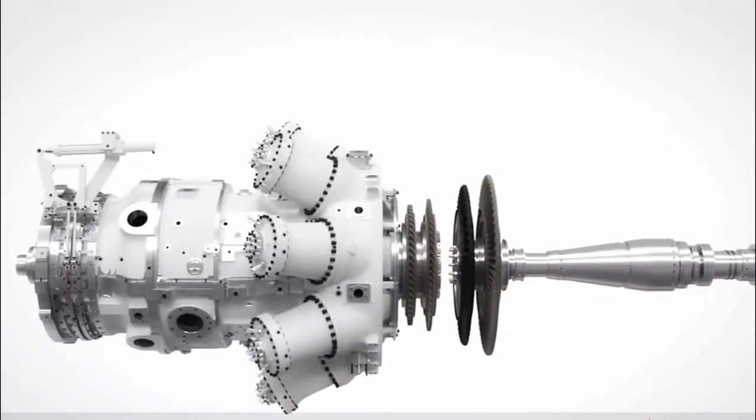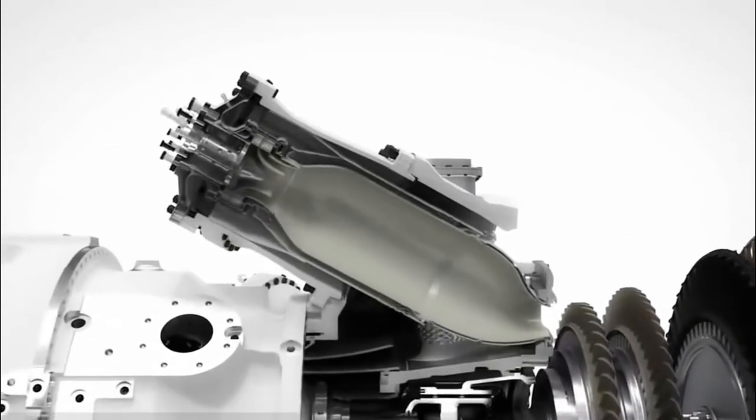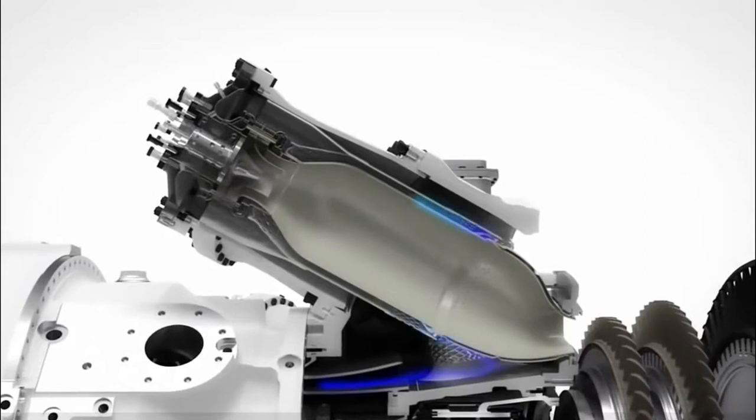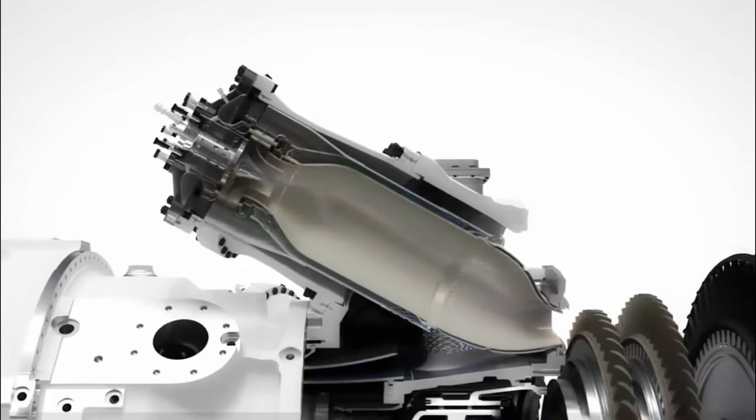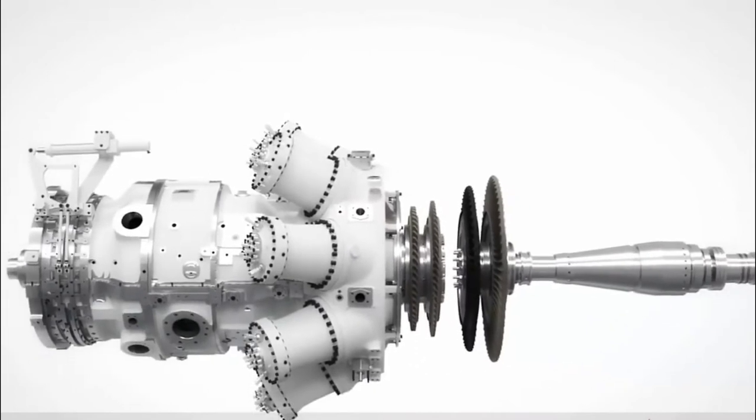The new combustor, featuring the fourth generation of DLE burners from Siemens. The burners are designed to further increase the power turndown range compared to its predecessors, maintaining NOx and CO emissions well within legislation levels. The DLE turndown capability enables the use of large single turbines, replacing multiple small units, allowing the same operating envelope. It offers robust and stable operation with dual fuel online switchover capabilities.